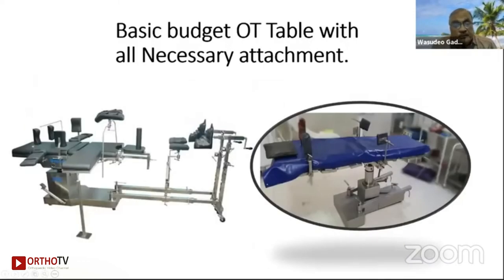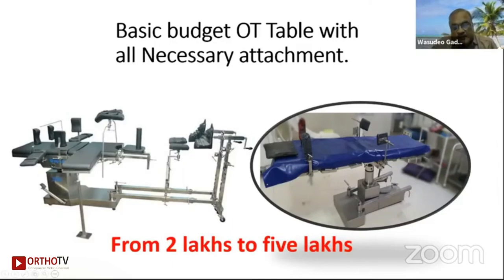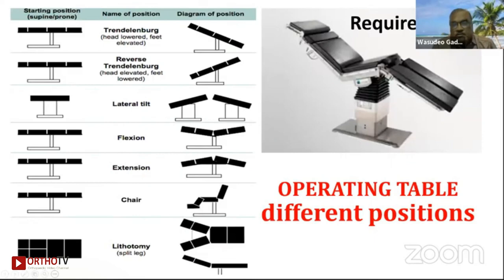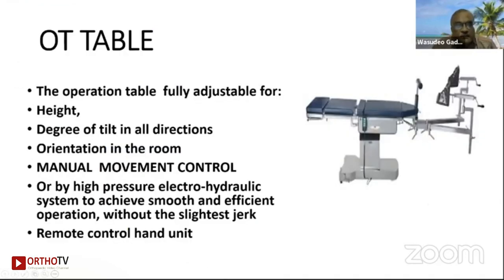The basic budget of an OT table with all necessary attachments is not very large. In the Indian market, you can get tables ranging from two lakhs manual to five lakhs hydraulic at reasonable prices. The requirement should be a segmented table — head, body, foot, and leg. There must be tilting, and you should be able to do reverse Trendelenburg, lateral tilt, flexion, extension, chair position, and lithotomy position — all fulfilled by one operation table.